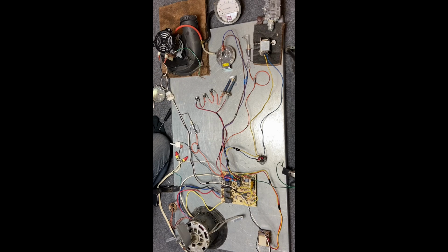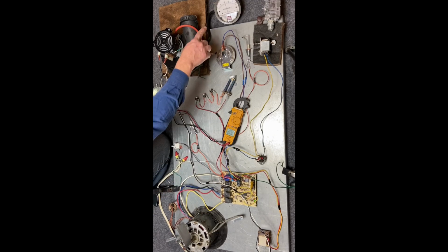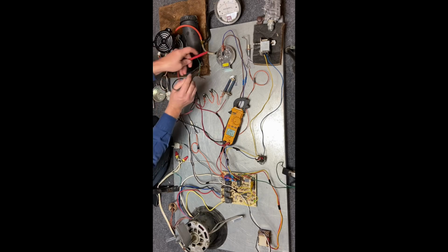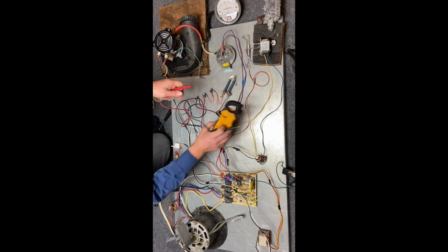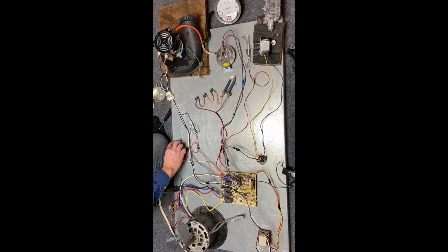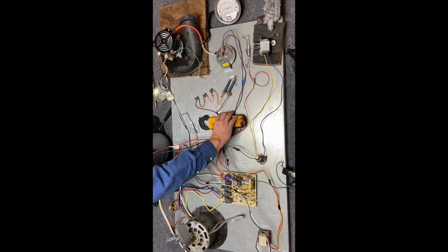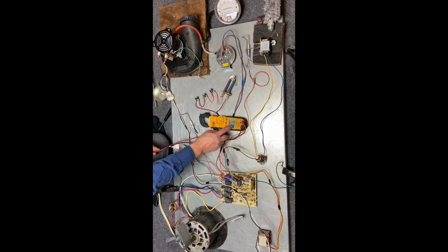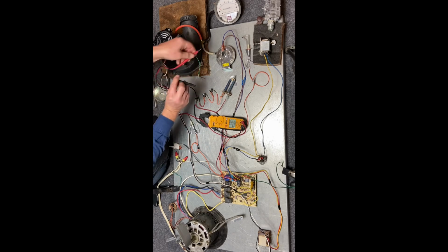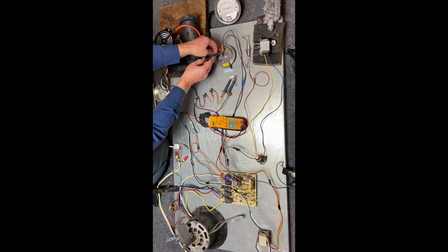So we're going to re-energize the system again. We can see we're pulling a vacuum. The switch should be closed. So I'm going to check my voltage. So next we're going to check this pressure switch. So what I'm going to do with this is you're going to see my meter. We're going to check voltage. And I'm going to put my meter on one terminal here and the other side here.